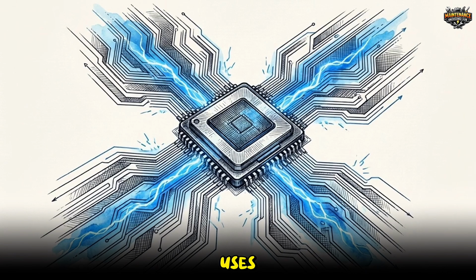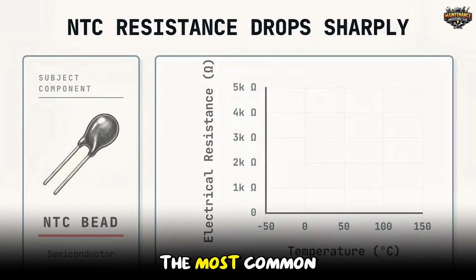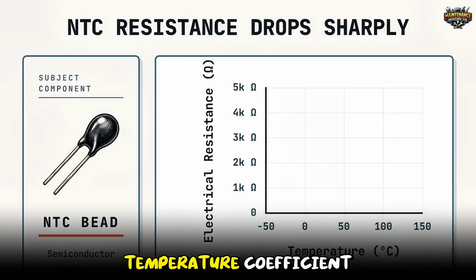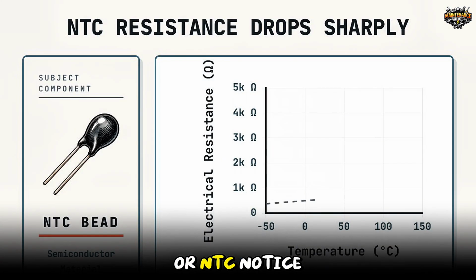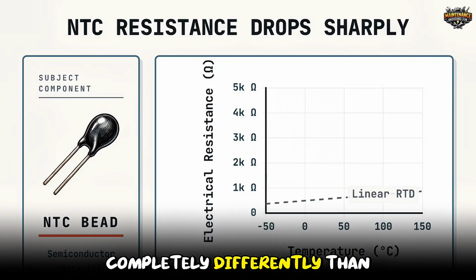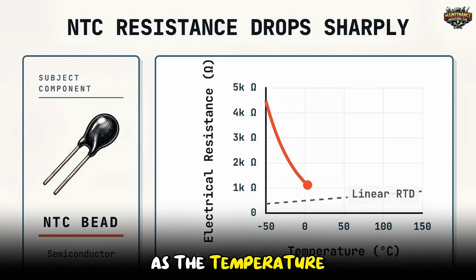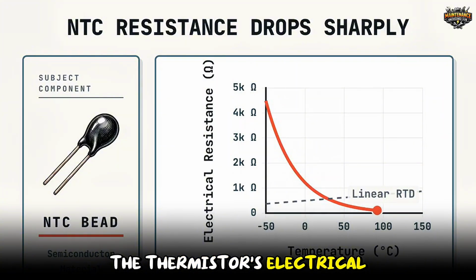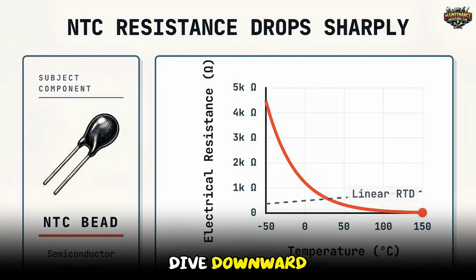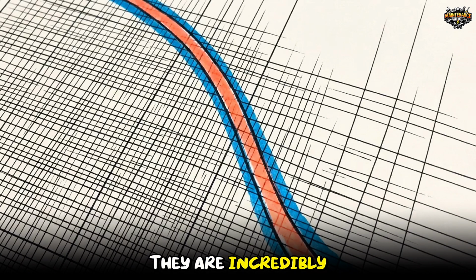The thermistor uses semiconductor materials to measure heat. This chart plots the behavior of the most common type, called a negative temperature coefficient, or NTC. Notice how it behaves completely differently than our RTD. Here, as the temperature rises, the thermistor's electrical resistance takes a sharp dive downward. Because of that steep curve, they are incredibly sensitive to even the tiniest shifts in temperature.